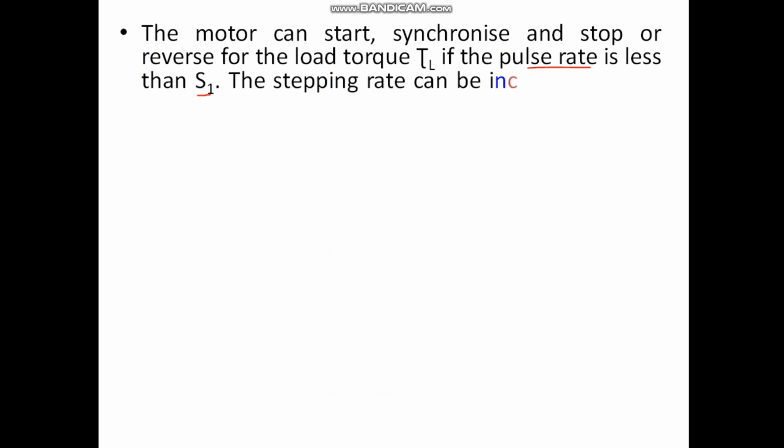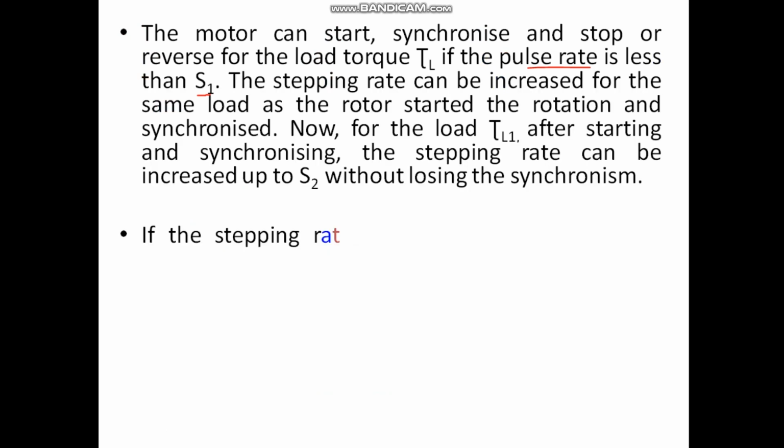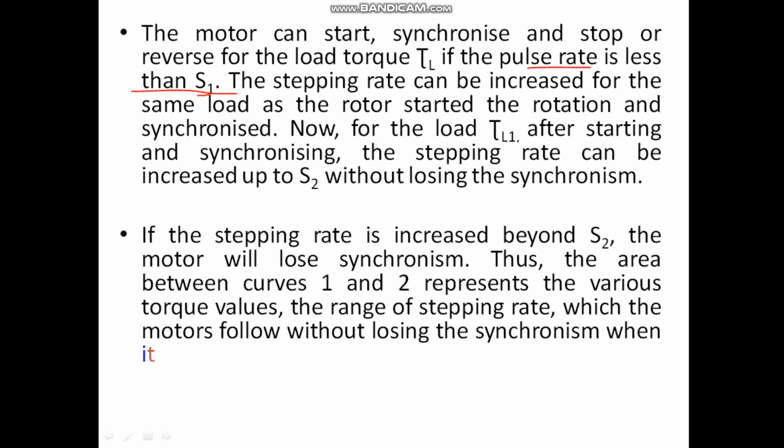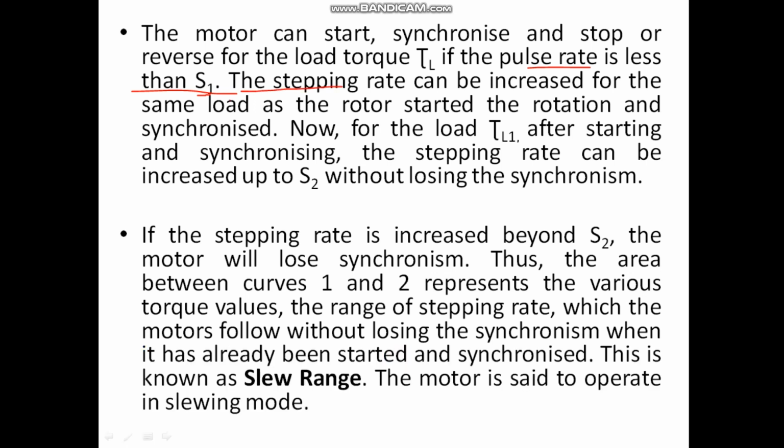The motor can start, synchronize and stop or reverse for the load torque TL if the pulse rate is less than S1. Now the stepping rate can be increased for the same load as the rotor has started rotation and synchronized. For the load TL1, after starting and synchronizing, the stepping rate can be increased up to S2 without losing synchronism.